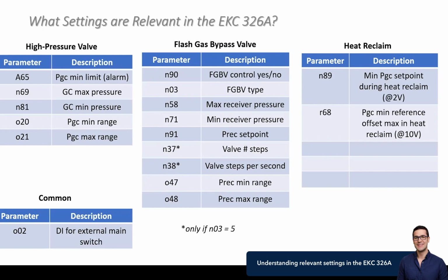If we're replacing the EKC, hopefully it's not because it's a completely dead system or dead controller where we can't see anything. If it is, we're starting from scratch in some regards. But if we do have the display available before we remove the EKC, we'd want someone to capture what the settings are for each of these parameters.